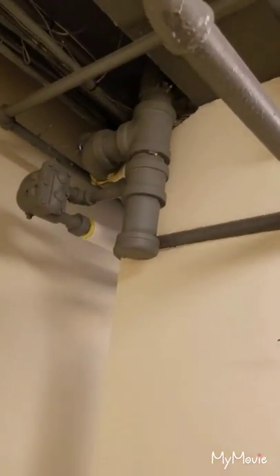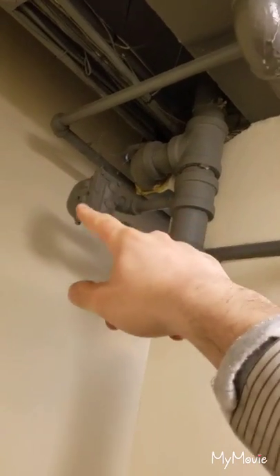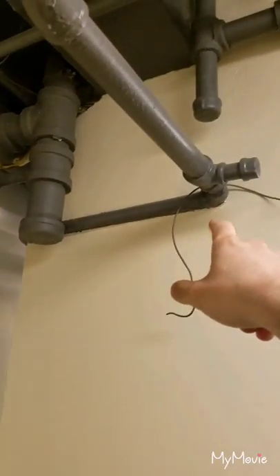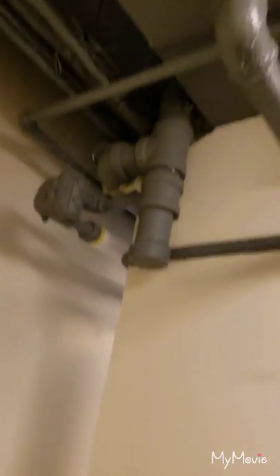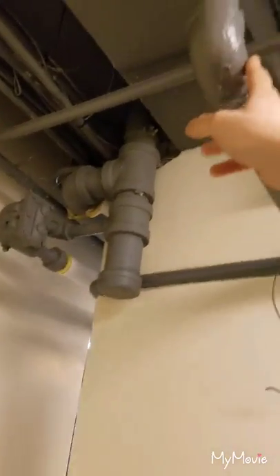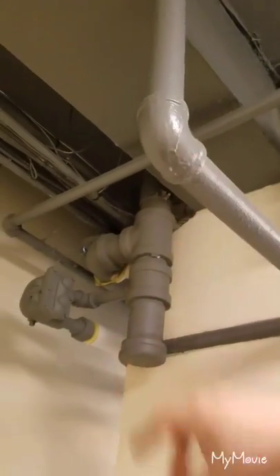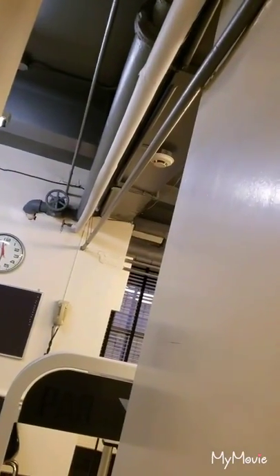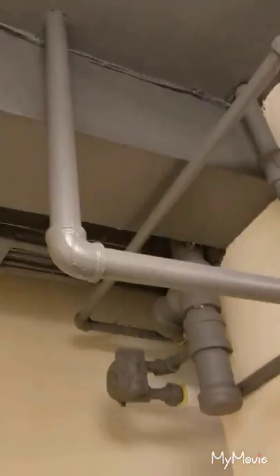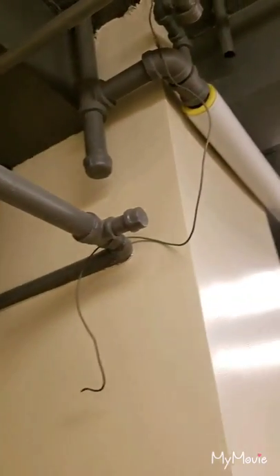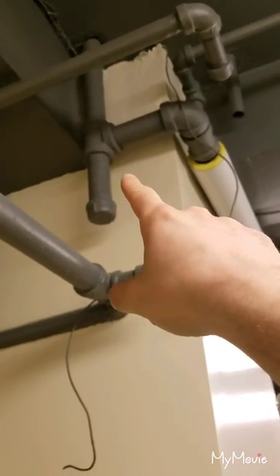same thing, main steam riser, ball lift steam trap off the bottom. Also, it seems that we have another line. Is this a steam line? No, this might be a gas line. I think there's kitchens in this line, so it could actually be a gas line. Yep, that's a gas line. Okay. That should be color-coded. That's the condensate return riser.